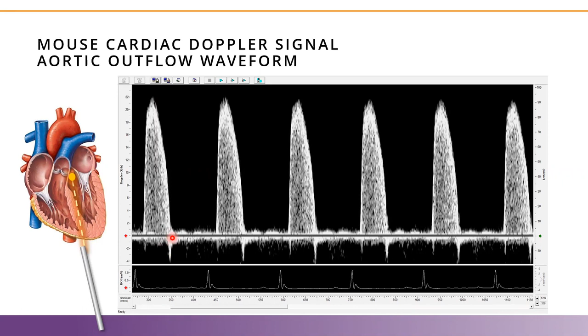So now, doing this measurement, how much data can I get out of this? Of course, you will get the maximum flow velocity measurement. But if you combine it with the ECG measurement, you will be able to get much more information out of it, like a pre-ejection timing, the time it takes to rise to the maximum flow velocity, the mean flow velocity, as well as the stroke distance.